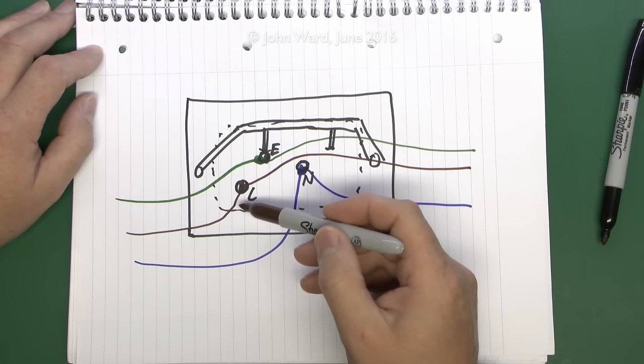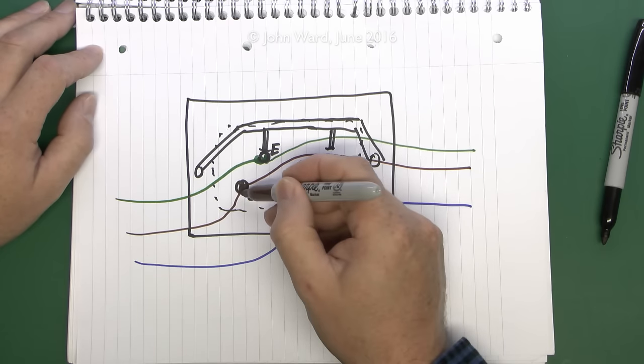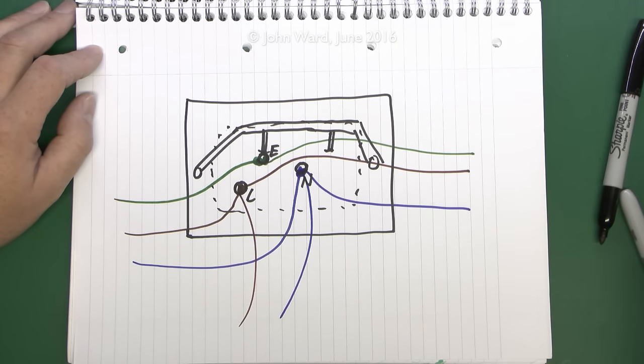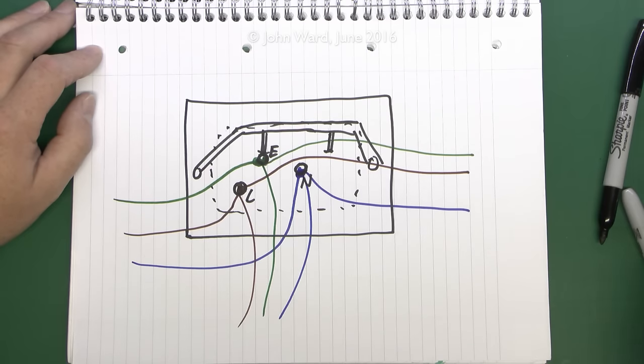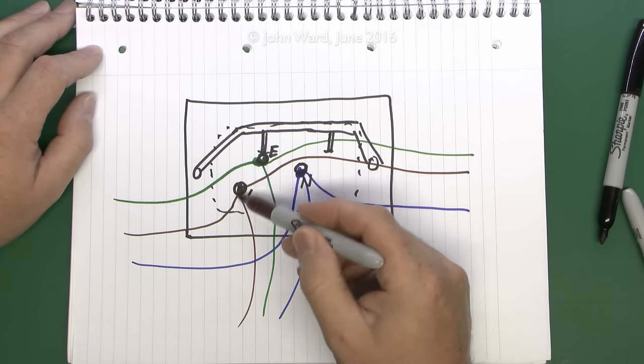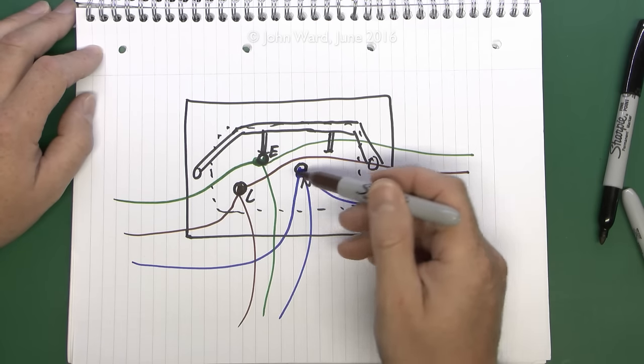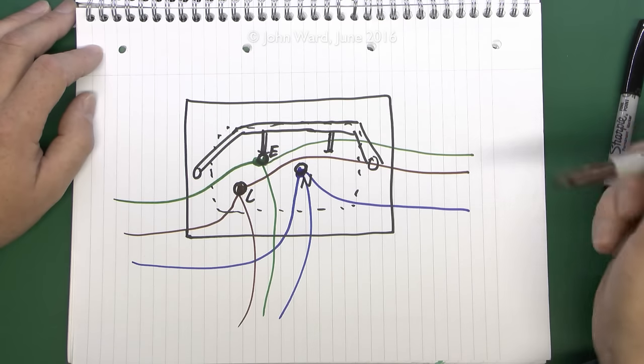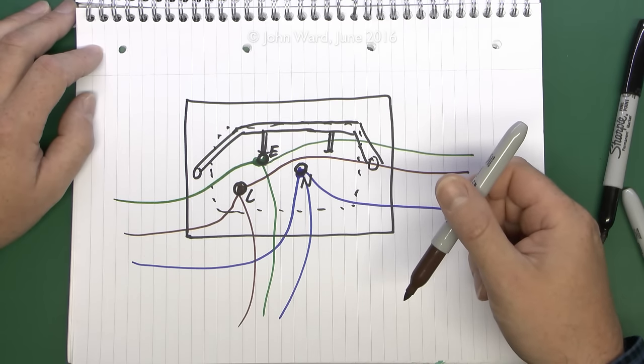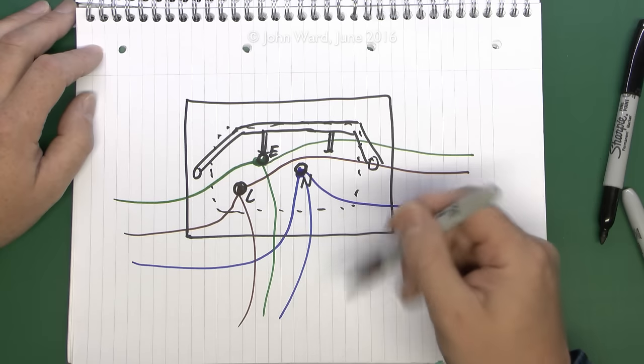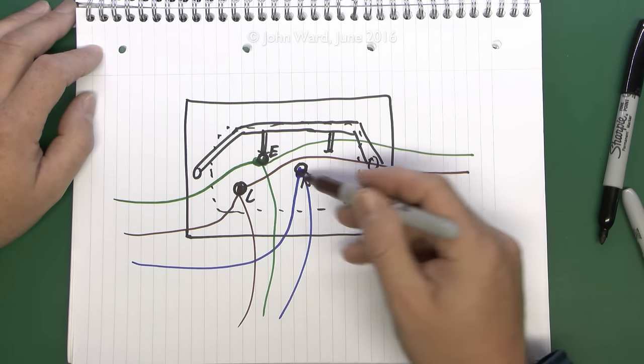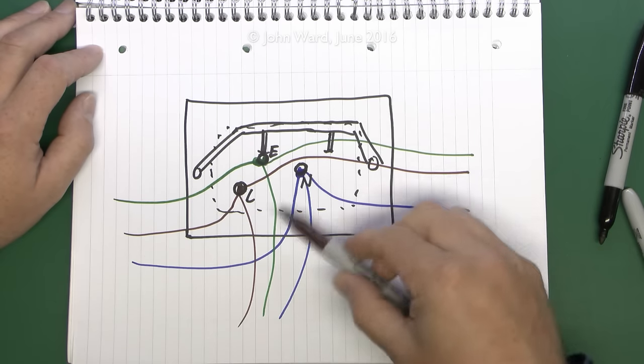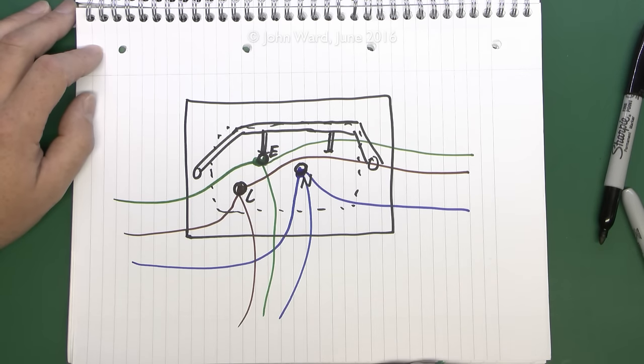If necessary you could connect a third cable in here, again exactly the same — your line would come off to a third cable, and the neutral and earth as well. The only restriction is how many wires you can actually get into the terminals and secure satisfactorily. Generally three is going to be about the limit, possibly four on some with bigger terminals, but anything beyond that is getting a bit silly. You'll have difficulty fitting them and making sure the screw actually holds them securely, but generally two or three wires is not a major problem.